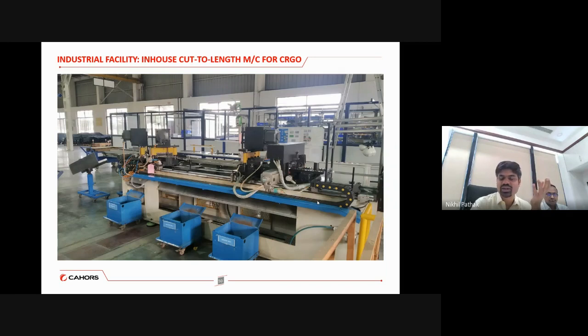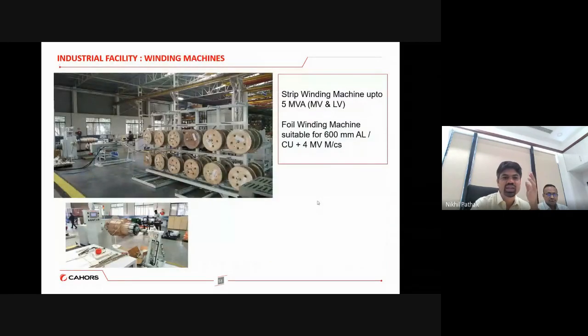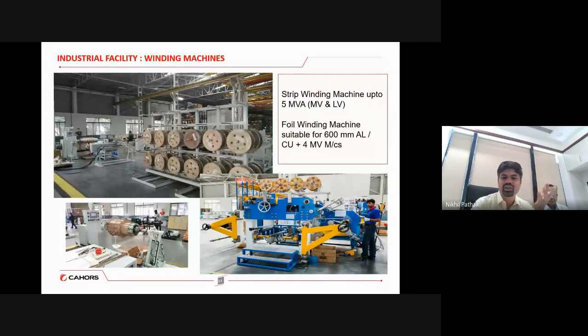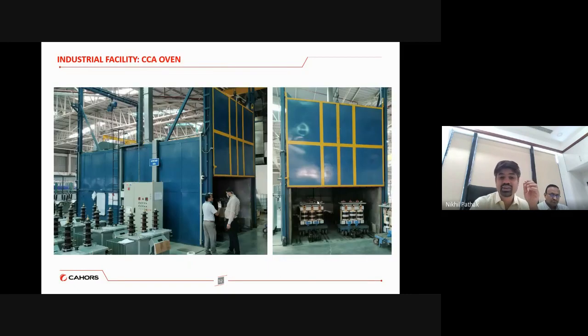We have an in-house cutting machine for CRGO. Then we have winding machines which are rated for 5 MVA. The strip winding machine is also there for MV and LV. Then we do have a foil winding machine, which caters to a foil size of around 600 mm. Then we do have a core coil assembly oven for the demoisturization process.